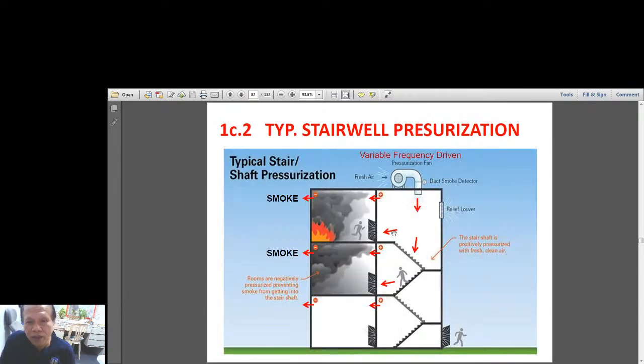So here is another drawing. You have the stairwell fan here at the top, and when it operates, it brings air inside the stairwell. So if you have a stairwell that is enclosed, you must have this fan, the stairwell fan, that would increase the pressure inside, so that the smoke from the rooms would not go to the stairwell, and therefore the people running out of those burning rooms will be able to exit much easier than when you don't have this. Because if you don't have this, definitely the smoke will come out of the exit door and it will suffocate the people escaping from the burning room.